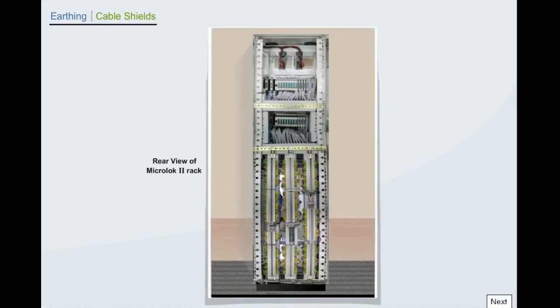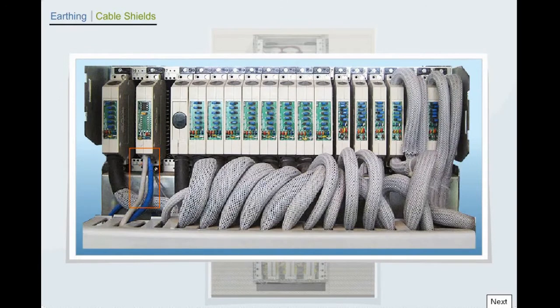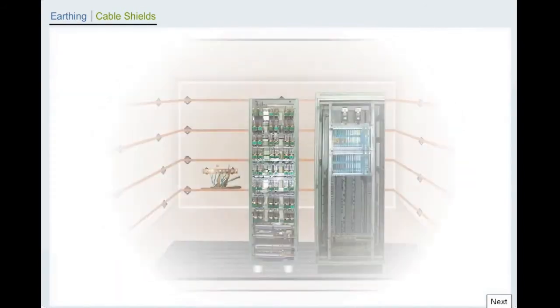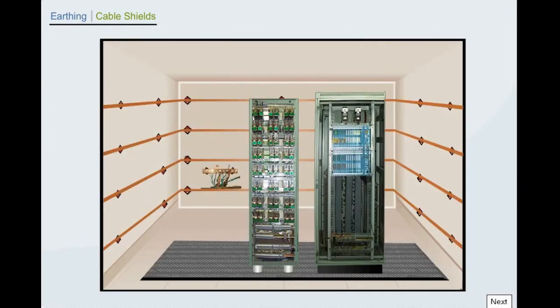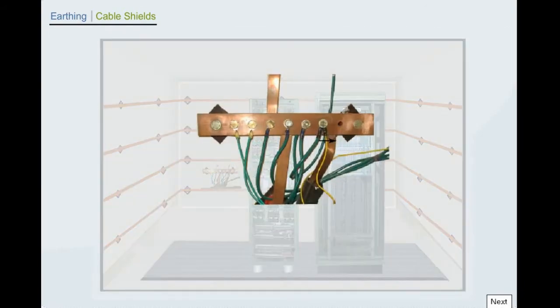Earthing, cable shields. Shielded cables should not be exposed in a particular location. These cable shields should be grounded at one end only. This end should be at the lowest impedance point with respect to room earth bar and the end closest to the room earth bar.